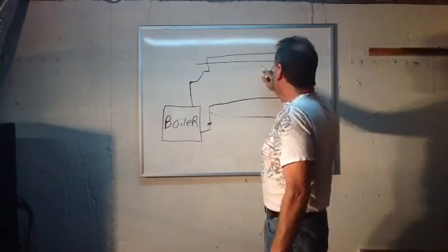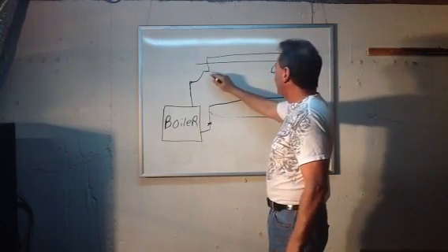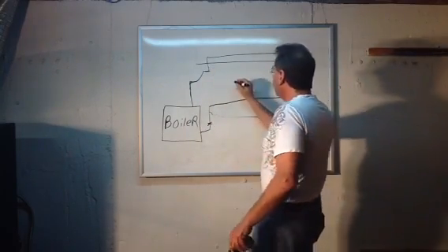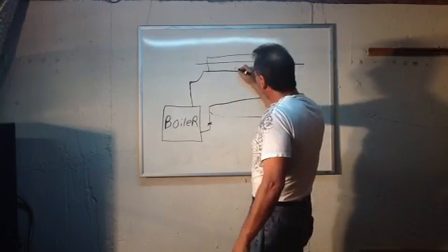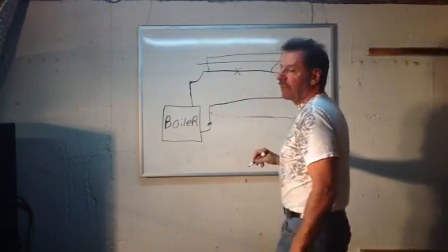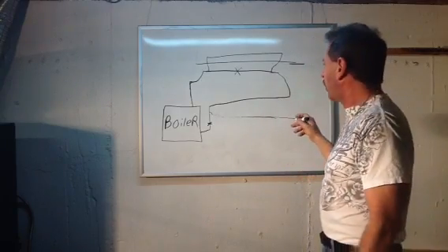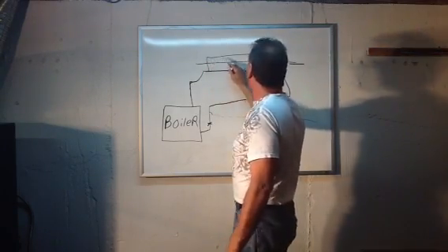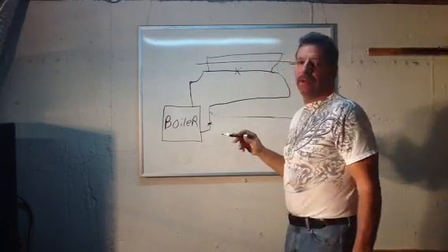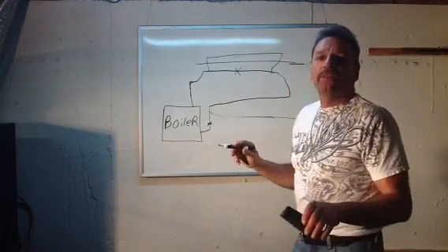That would be how you would get the baseboard to get hot again, by either cutting those tees out. Or if they did do it on monoflow tees and you're not sure what's going on, you can simply cut a valve right there in the basement in the middle of the pipe and shut it off. That would cause the water to stop at the valve and go through and around, and you'd see that the baseboard would get hot instantly.